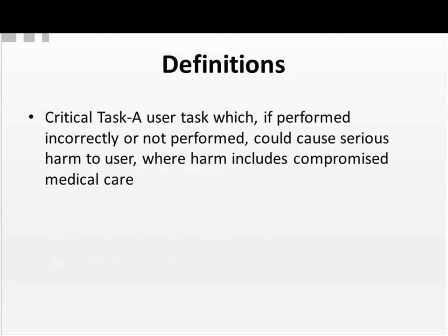Critical task is a user task which, if performed incorrectly or not performed, could cause serious harm to user, where the harm might include compromised medical care. So harm can be a harm directly to the user, or it could include compromised medical care or no medical care.